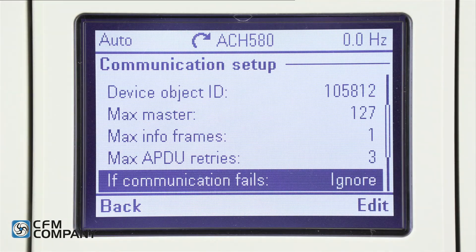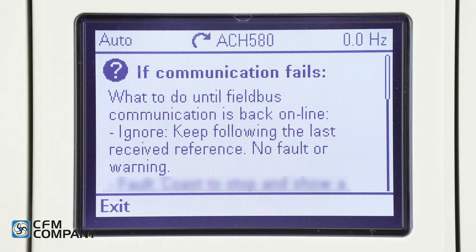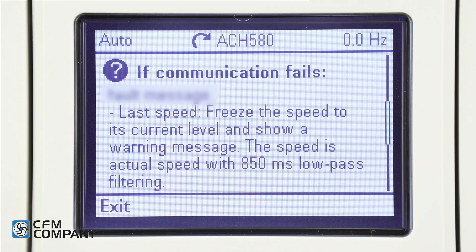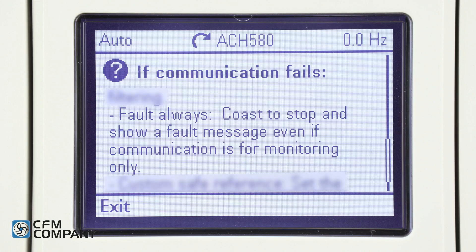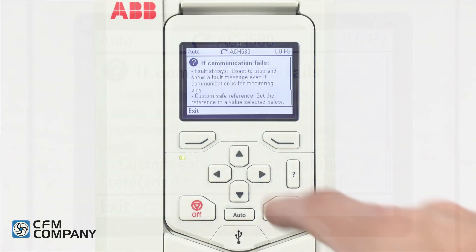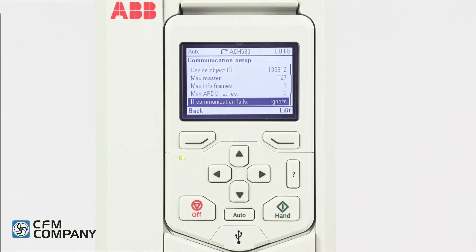Next is if communication fails. Press the question mark button to see the options: Ignore — keep following the received reference, no fault or warning. Fault — coast to stop and show a fault message. Last speed — freeze the speed to its current level and show a warning message; the speed is the actual speed with 850 millisecond low-pass filtering. Fault always — coast to stop and show a fault message even if communication is for monitoring only. Custom safe reference — set the reference to a value selected below. Press exit to return to the communication setup menu.